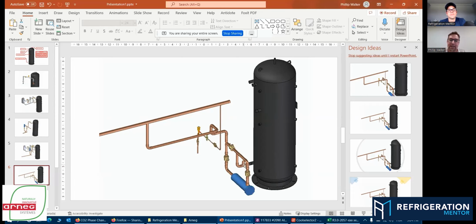We came off here, we do the bend. You can see there's a connection here, which is the next page, because this is connected to our backup unit. But this is all intentional. What we want to do is create a good liquid column to feed that manifold, so we have good liquid feed. Because what all TXVs do not like, electronic TXVs especially, is poor liquid feed. They operate erratically. And you can see that in the graphs, right? With improper liquid feed, the TXVs are opening and closing, and we're unable to properly maintain the display case. So working on a system, you see this is intentional, guys, for all the reasons we just spoke about.